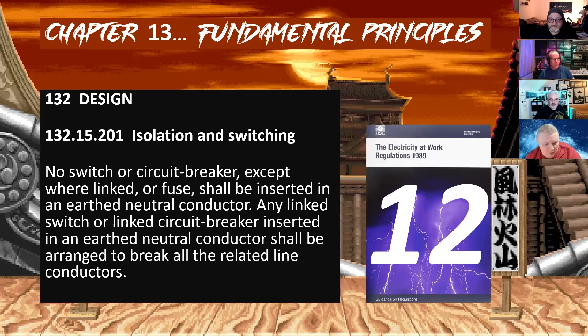This is massively contentious with diverted neutral current at the moment, because we know we have earth conductors and bonds that are now carrying neutral currents. They may be network neutral currents, or partly installation neutral currents. It's a bit of a mess at the moment, and I've had chats with some senior people at JPEL about this. I really hope there's going to be more guidance, because this is a known hazard and I don't think the industry's got an answer for it, since accountability sits with the DNOs. I see the outcome being something like external meter blocks being mounted in insulated enclosures, which is already being done now by a lot of the DNOs, with earth bars now insulated, proactively for sparks too, doing fuse upgrades and similar work.